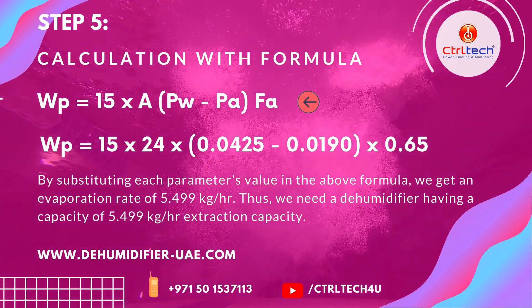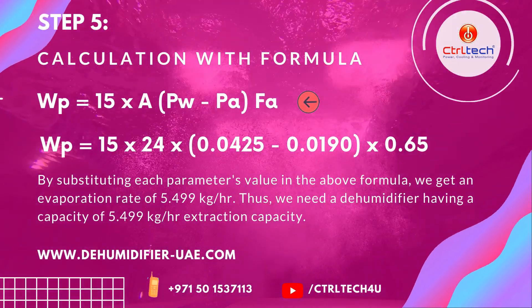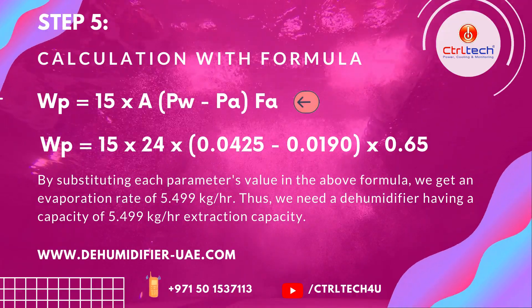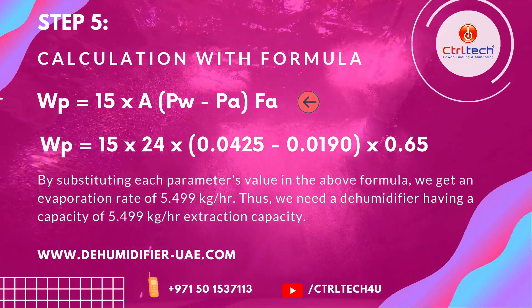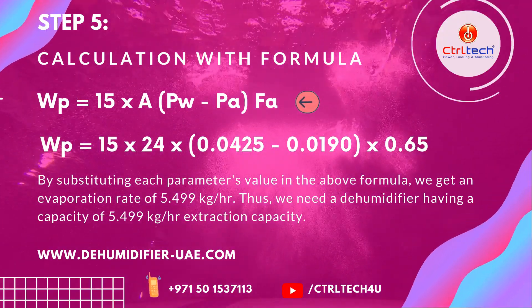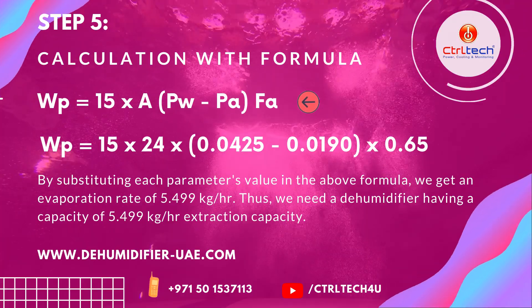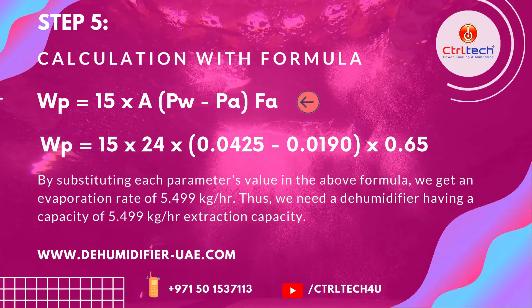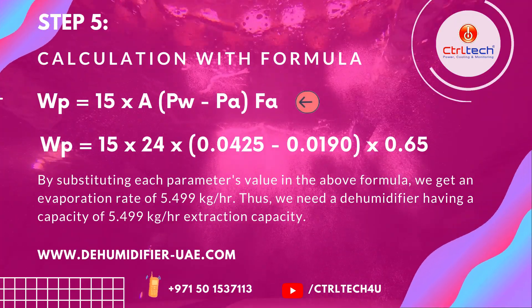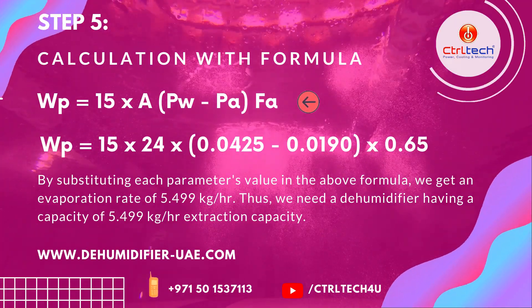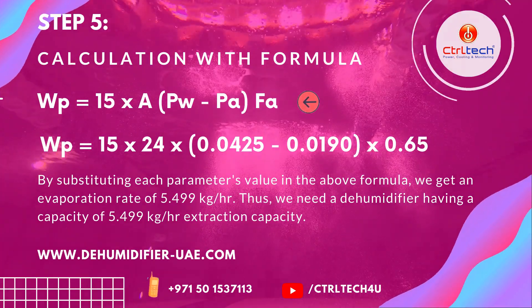By substituting each parameter's value in the above formula, we get an evaporation rate of 5.499 kg/hr. Thus, we need a dehumidifier having a capacity of 5.499 kg/hr extraction capacity.